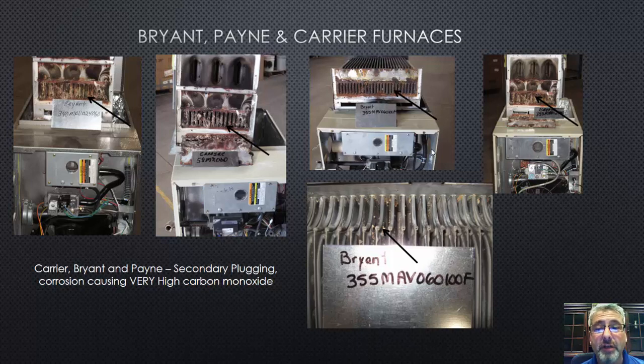That's very important. Another item you must understand, and this is so important, is that when you replace a secondary on one of these furnaces, there is an update kit. The coupler box on the back must be replaced. You must do the proper setup.